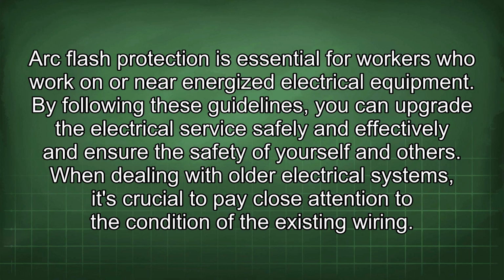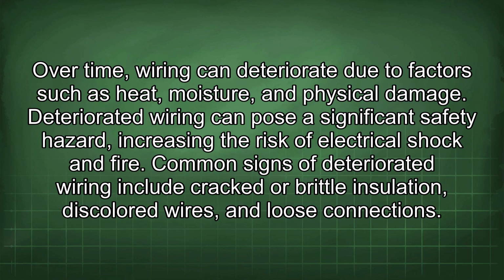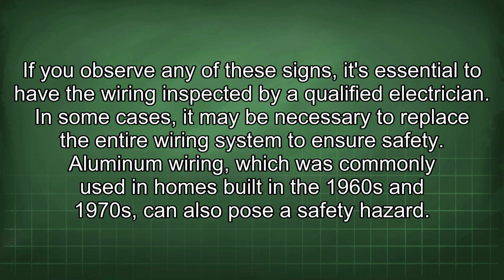others. When dealing with older electrical systems, it's crucial to pay close attention to the condition of the existing wiring. Over time, wiring can deteriorate due to factors such as heat, moisture, and physical damage. Deteriorated wiring can pose a significant safety hazard, increasing the risk of electrical shock and fire. Common signs of deteriorated wiring include cracked or brittle insulation, discolored wires, and loose connections. If you observe any of these signs, it's essential to have the wiring inspected by a qualified electrician. In some cases, it may be necessary to replace the entire wiring system to ensure safety.